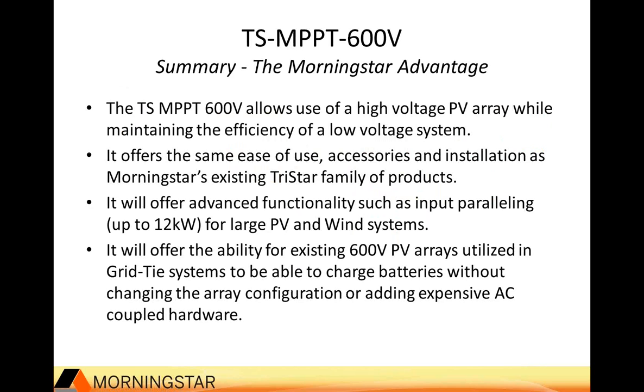So in summary, the 600 volt allows a high voltage PV array to be utilized with a low voltage system. We think that offers new opportunities for ease of wiring. It allows customers that are familiar with high voltage strings to utilize the same type of array wiring that they've always been using, except now they can use it with a charge controller and charge a 48 volt battery. It offers the same ease of use, accessories, and installation options that the existing TriStar family of products from Morningstar has offered. It gives you advanced functionality such as input paralleling, which is a bit new to charge controllers in the industry, so you can utilize very large PV and wind systems. And it also offers the ability for a 600 volt PV array that's already in an existing grid tie system to be transferred over to charge batteries without changing the array configuration or adding any kind of expensive AC coupled hardware. So we're looking forward to supporting those applications a lot in the future.